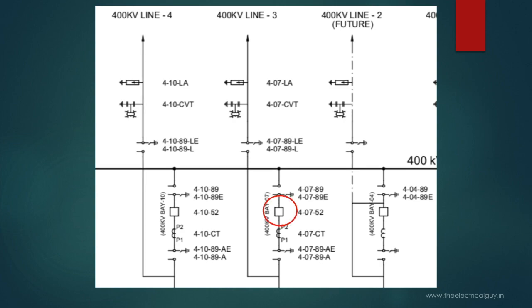So let's say I want to carry out the maintenance of this circuit breaker. In such cases it is a safe practice to completely disconnect this breaker from the supply. And hence to do so I will open both of these disconnectors which will completely isolate this breaker from the supply. Now the maintenance work can be carried out without any worry.